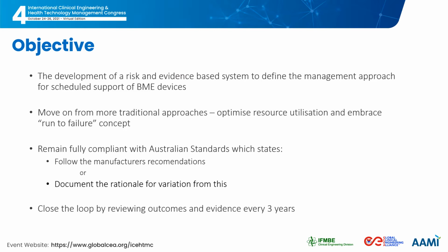We thought it was well and truly time to move on from what were some more traditional approaches, and these included things like strictly following manufacturers' recommendations or checking everything every 12 months, and really move towards optimum resource utilization, and certainly embrace the concept of run to failure, which is something which had been gaining momentum internationally for some time.